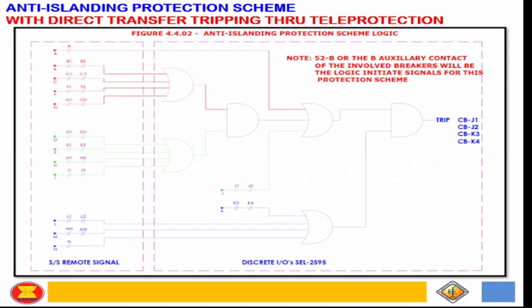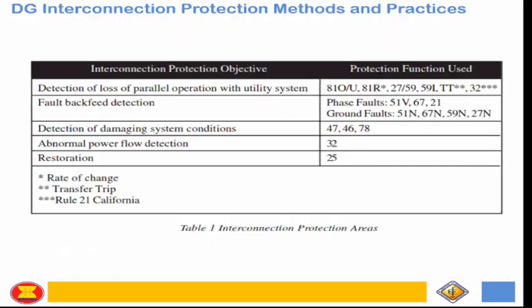Then there's transfer tripping. If there is communication between the distribution utility and the DG, there is a scheme that initiates transfer tripping, ensuring the DG is isolated, because with reclosing implementation, the distributed generation must really be de-energized or isolated when we restore power. So that's the scheme we require for anti-islanding. The DG owner may not understand it, and it is very expensive because you need to invest in communication facilities as well as RTUs and so on.